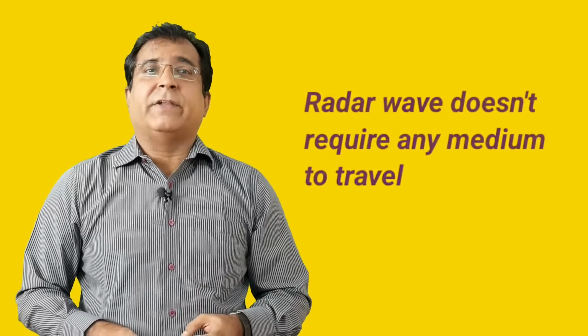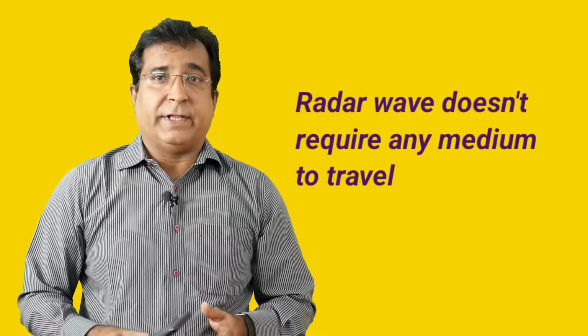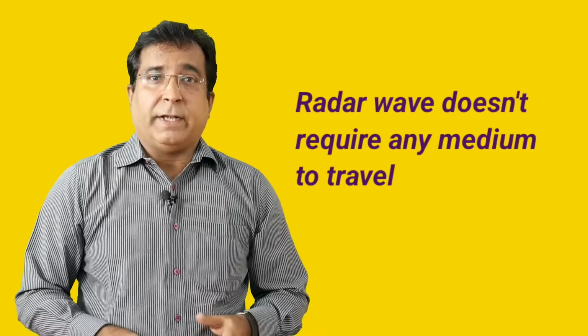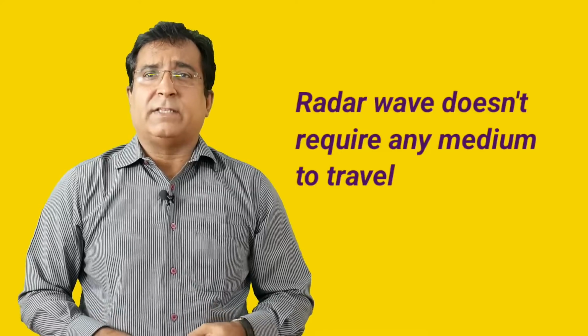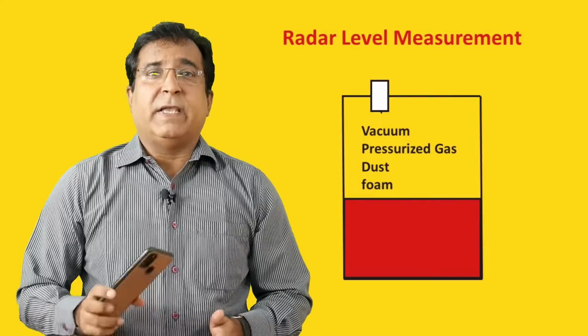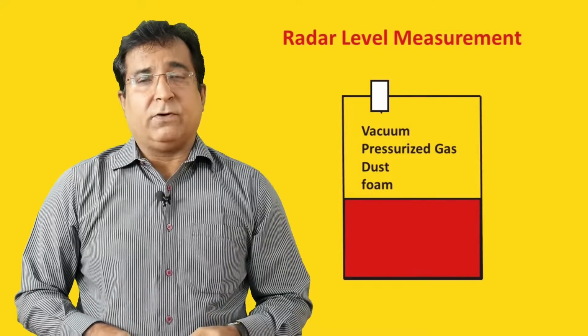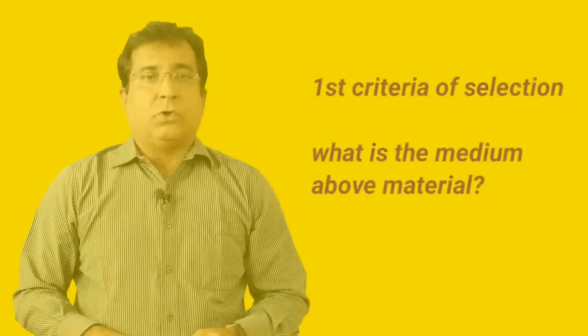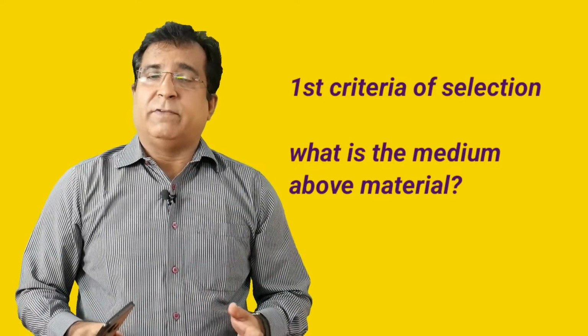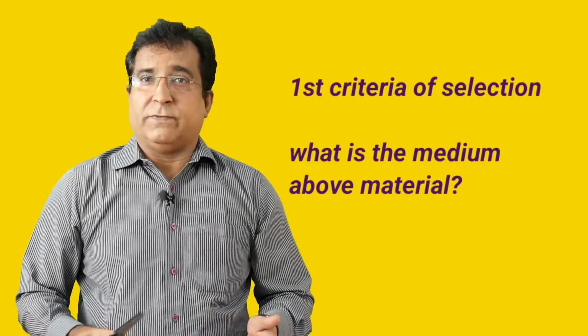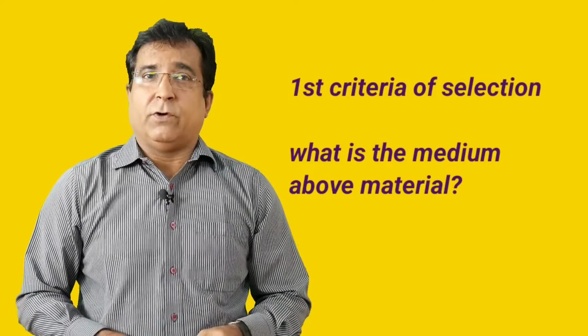While in radar, this is not the condition, as electromagnetic waves travel in a vacuum too, or in air or vapor at high pressures. And it is not, or only very slightly, affected by foam, vapors, powder and dust above the material. This makes the radar sensor a better choice for this application. So my first and most important selection criterion will be what is above the material: is it vacuum, air, pressurized air, gas, vapor, or whatever.